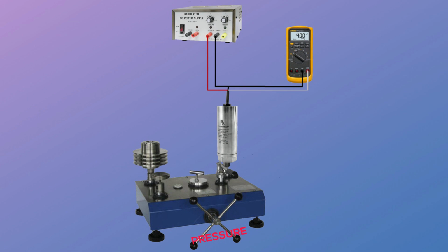First, the pressure transmitter is plumbed in line to the pressure source and standard. Using a deadweight tester, the unit under test would be plumbed into the output pressure line as shown. The transmitter is then electrically powered and attached to a reading device. Here, we show a loop-powered 4 to 20 milliamp device in line with the power supply and digital multimeter.